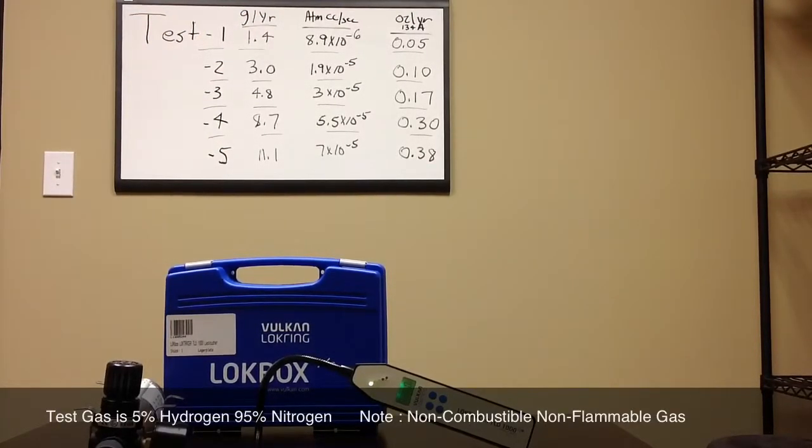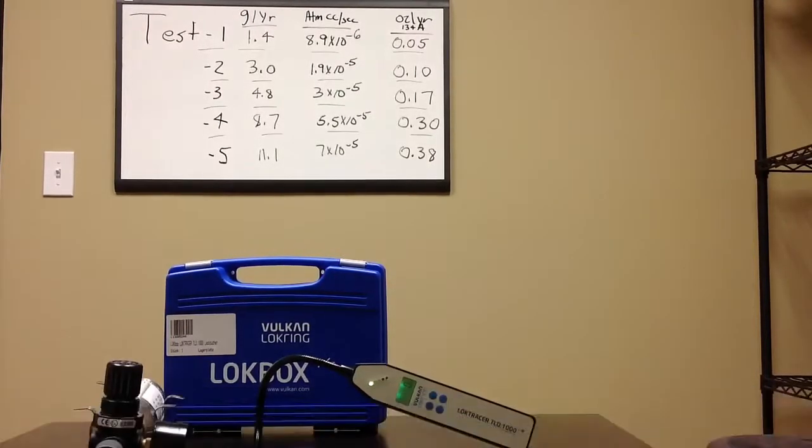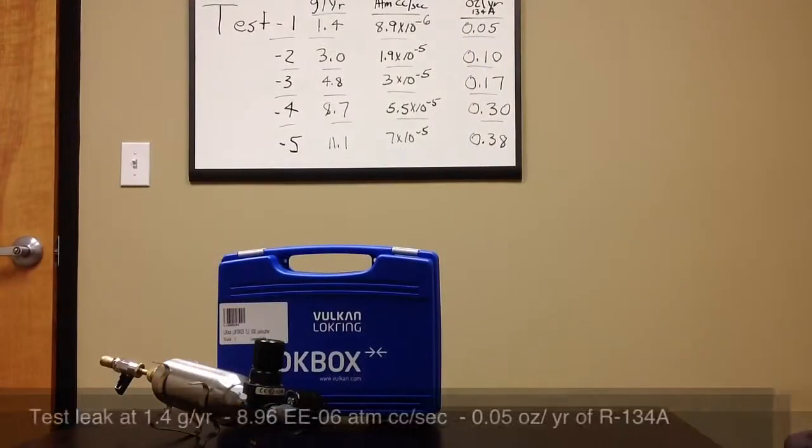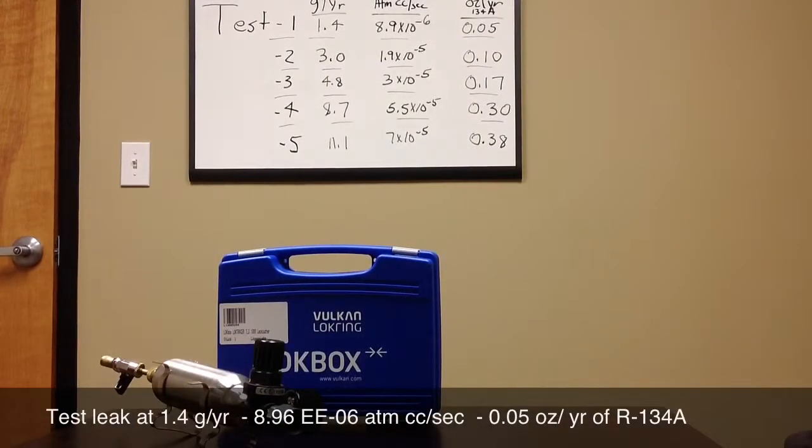So that's a very small leak and we'll progress as we see down the way here. Let's get started. Our first test will be at 1.4 grams per year, that is 8.9 times to the minus 6 atmospheric cc's or 0.05 ounces per year R134A.